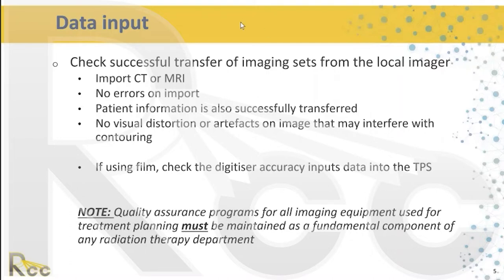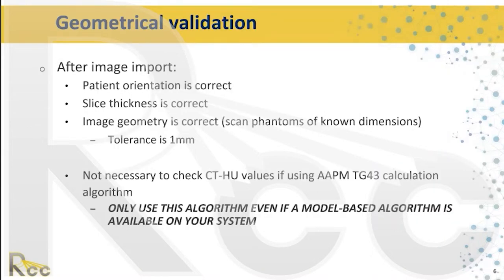QA programs for all imaging equipment feeding information into the planning system must be maintained with routine quality assurance. For geometrical validation, once data is imported into the treatment planning system, we must verify that the patient orientation is correct, slice thickness is correct, and that the image geometry accurately reproduces phantom dimensions within the planning system. The tolerance for this is typically around a millimeter.